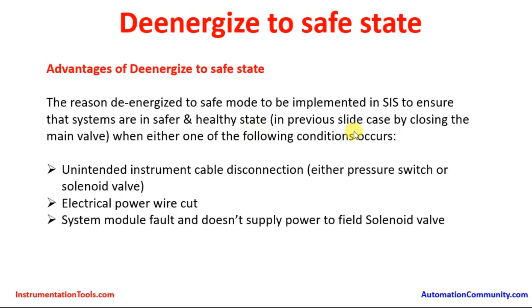In the previous slide case, the main valve closes when either one of the following conditions occurs. Whenever there is an unintended instrument cable disconnection — either at the pressure switch or the solenoid valve — the pressure switch works as a sensor and the solenoid valve is the final control element output. If there is a cable disconnection in any one of these, it loses the signal going to the logic solver and the output to the solenoid valve gets disconnected, thereby removing power and moving the valve to the closed position.